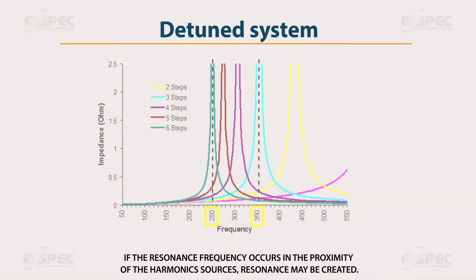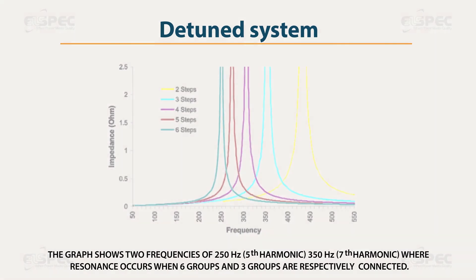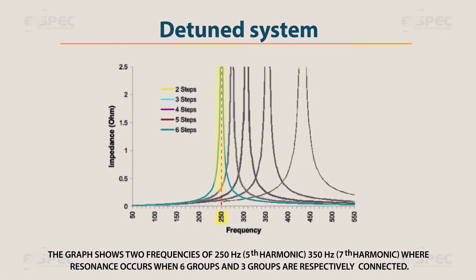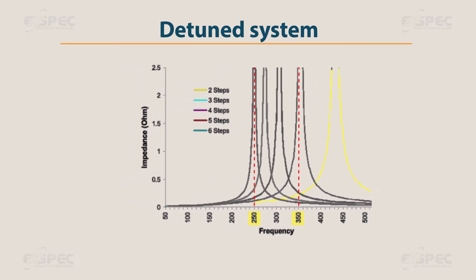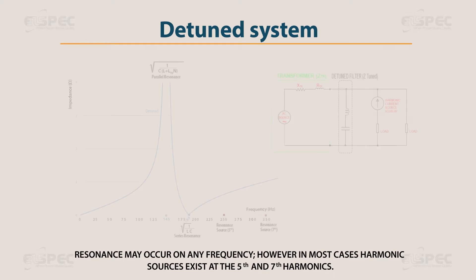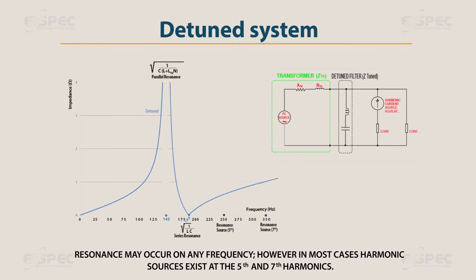If the resonance frequency occurs in proximity of the harmonic sources, resonance may be created. The graph shows two frequencies — 250 Hz (5th harmonic) and 350 Hz (7th harmonic) — where resonance occurs when 6 groups and 3 groups are respectively connected. Resonance may occur at any frequency; however, in most cases, harmonic sources exist at the 5th and 7th harmonics.